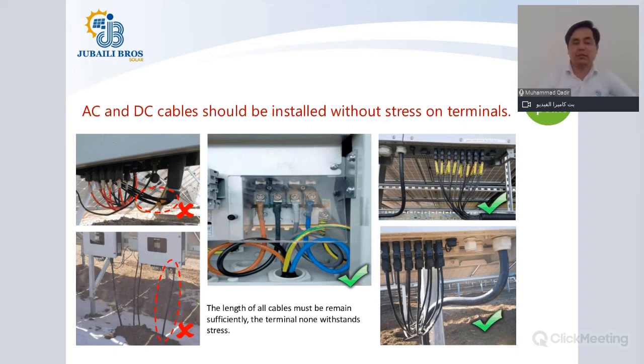Similarly, in the picture, at the left bottom corner, the cable is connected very tight, and this is again putting a huge stress onto your solar inverter. At the center, you can see the cables inside the maintenance compartment are kept loose, which is very good, which is not putting any stress on the connection points. Also, in the future, if you are cutting your solar cables for some maintenance purposes, you will still have some extra length of solar cable which you can use to accommodate such maintenance purposes.